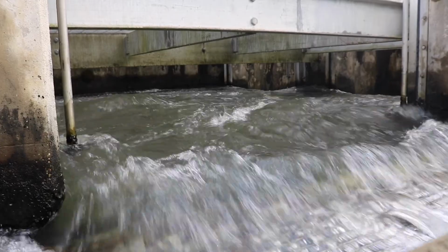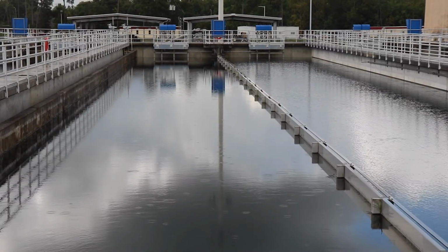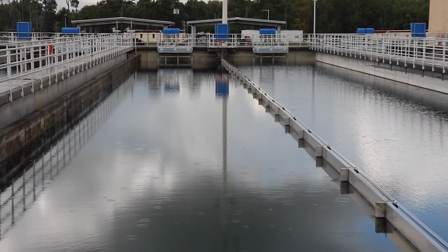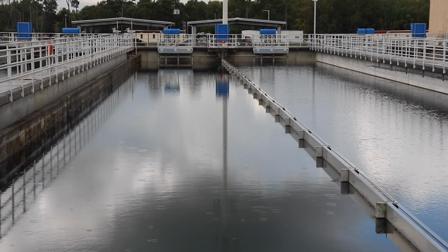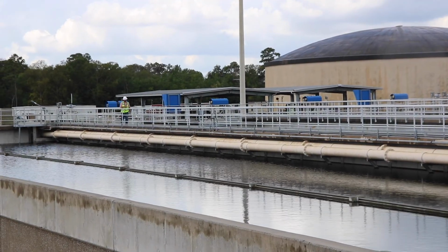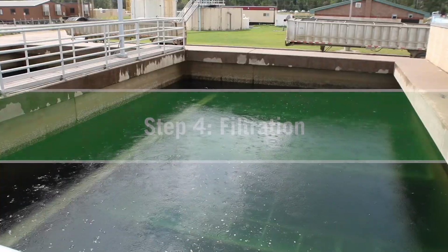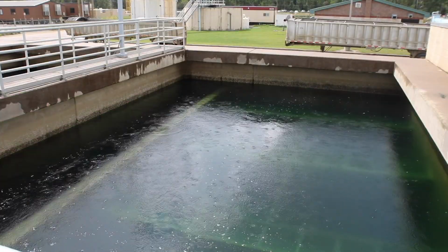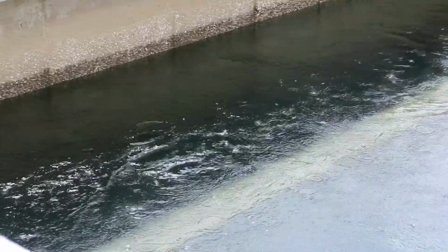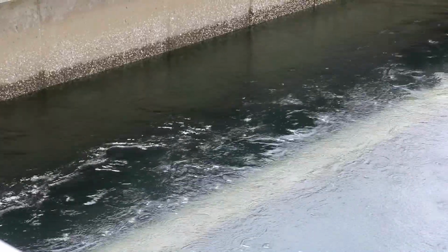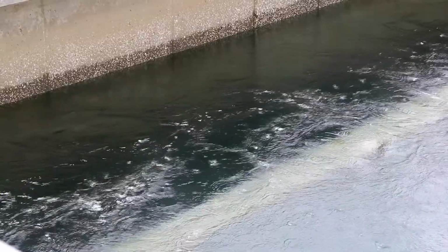Step 3. Sedimentation. Next, the water is moved to the sedimentation basin, where the water moves very slowly and the floc settles to the bottom of the tanks, and the clean water moves to the next step of the process. Step 4. Filtration. Once the floc is removed, the water is filtered through a sand filter. All the particles are removed to make the water clear.